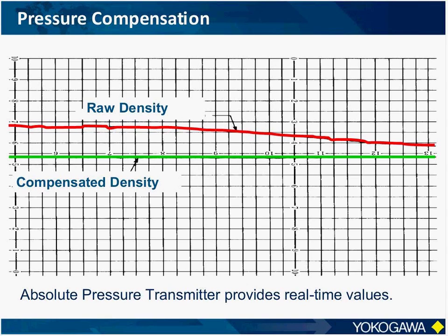This illustration shows a gas stream whose constituents, its stream components, remain the same, but the pressure of the process is gradually decreased. This results in a decrease of raw density at process condition, but the analyzer calculates the compensated density, which remains unchanged.